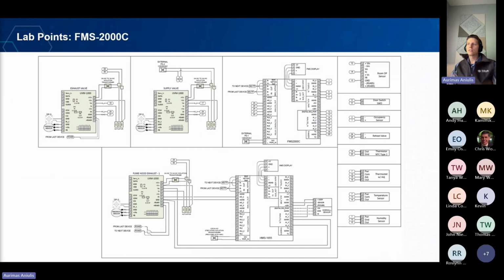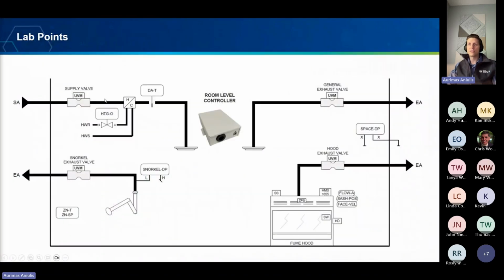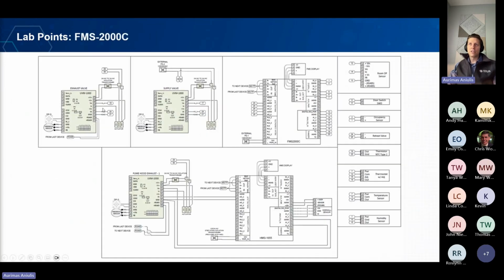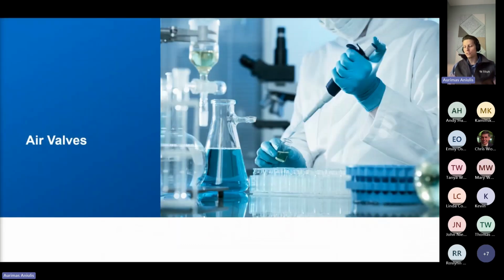This is a wiring scenario showing all the different points. You have your exhaust valve brain, the UVM as we call it, which represents universal valve module. That's the valve brain, and you can see how the points land on the exhaust, the supply, and the fume hood exhaust. This is the fume hood controller, the HMS 1655. This is the room level controller, FMS 2000C. And of course, you've got your auxiliaries: your room differential pressure sensor, your door switch, your occupancy sensor if you're using one, your reheat valve, and thermistors, thermostats, temperature sensors, and humidity sensors. So these are the same ingredients used in an application in various different ways to satisfy application requirements.